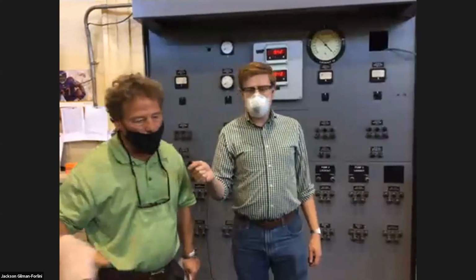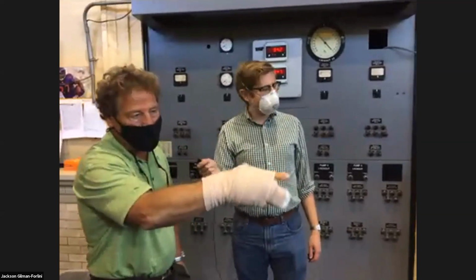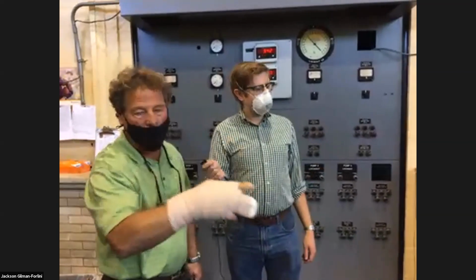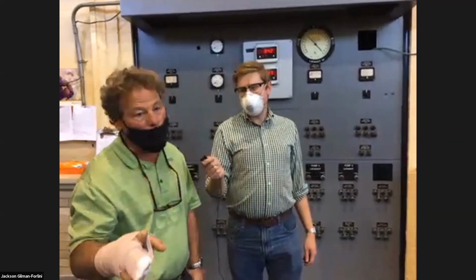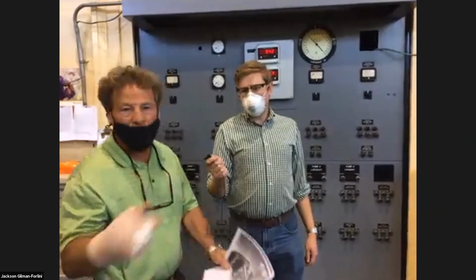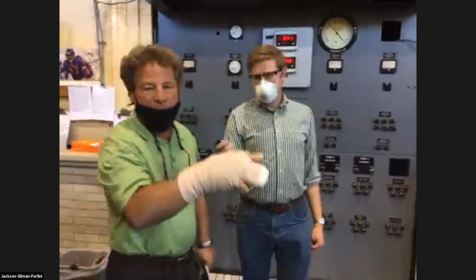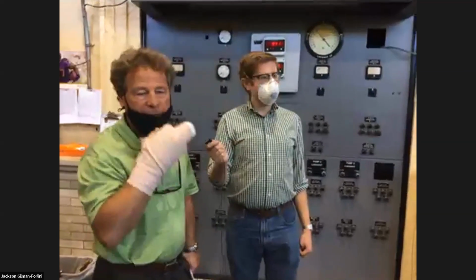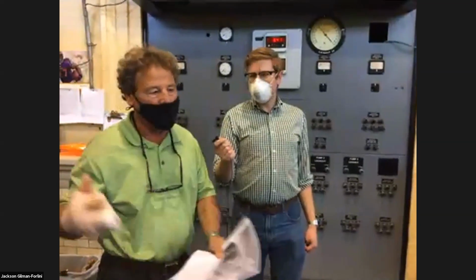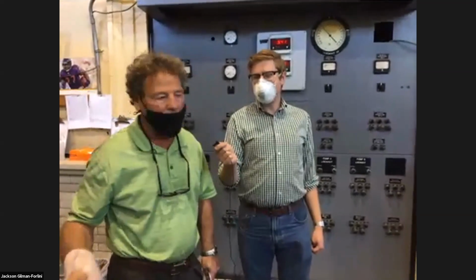If any of these pumps failed or there was an electric failure, that sixth pump used to be driven by four diesel engines, which would in turn pump it, but the big no-no is that it would pump it straight through the harbor. Well, of course, that is no longer environmentally acceptable practice, so that function has been deleted.